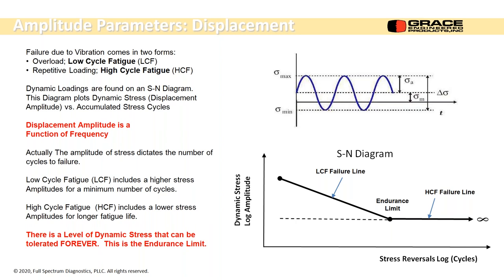Low cycle fatigue can usually be designed out, but there's something that's changed recently in the power industry. They're not using main coal power plants as baseload anymore. They're using a lot of them as peaker plants. You have all these really big pieces of equipment, a lot of forced draft and induced draft fans, and they're not made to start and stop. You start them, and two years later you turn them off at the outage. But now they're starting and stopping every day.